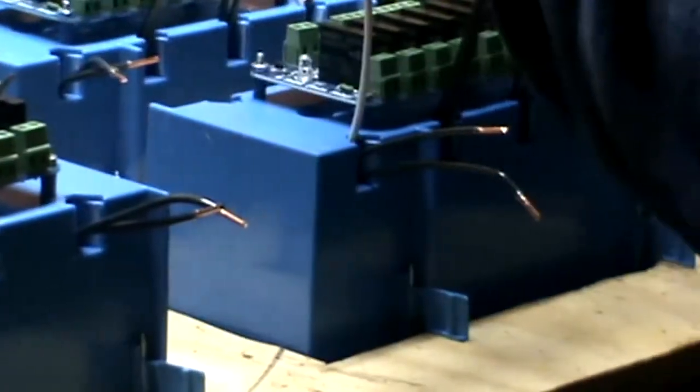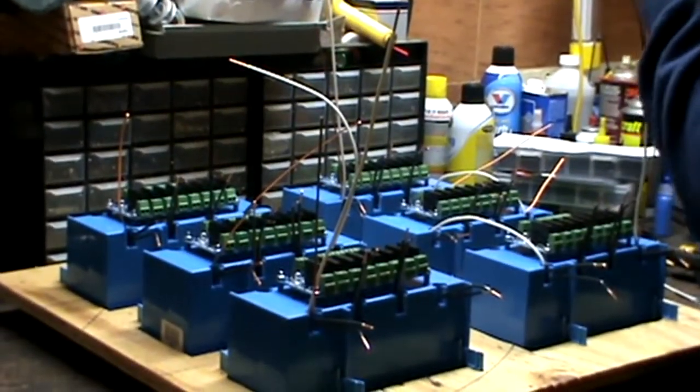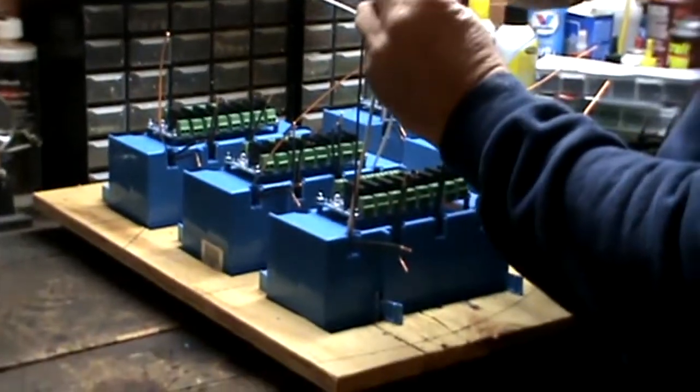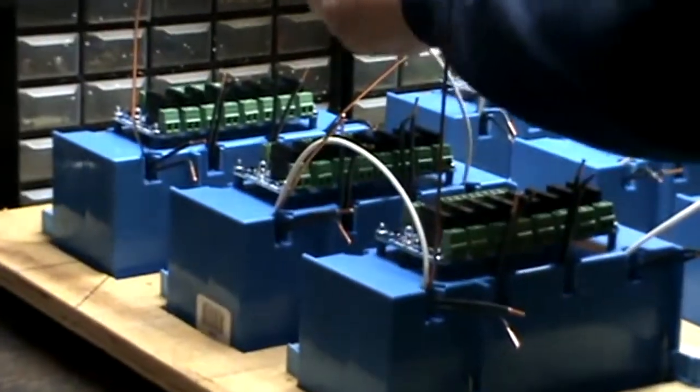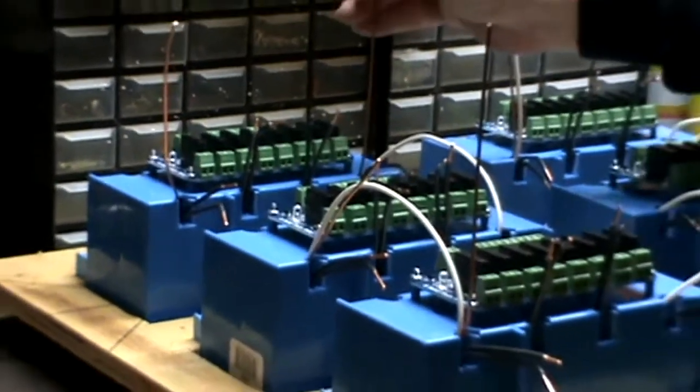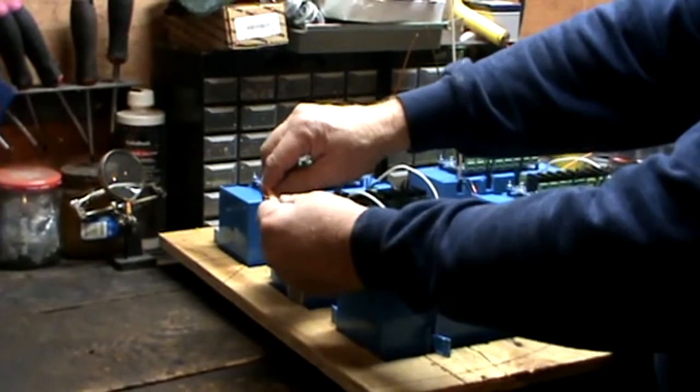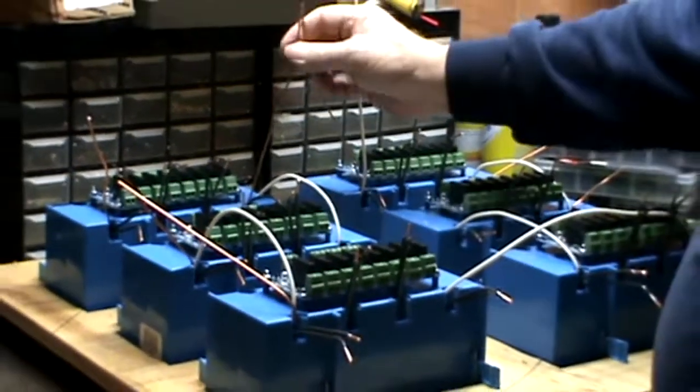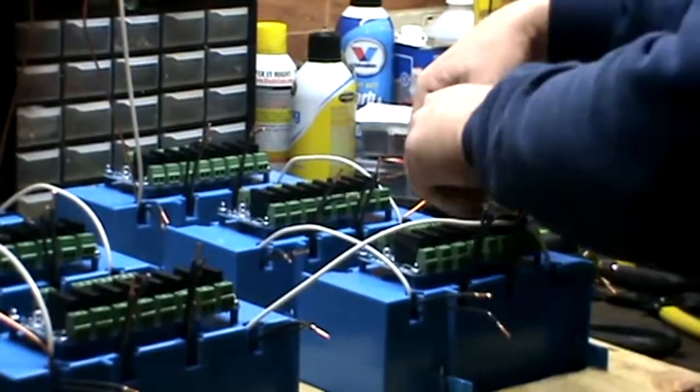Down here, the one on the left, I'm going to slip into the next box. The one on my right, I'm taking it all the way across to the box on the opposite side. Over here, this common simply goes up to the next box, and this one goes to the last box. Now I also have a ground on the opposite side right here. I'm going to connect these two together. Then out here on the side, I'm going to connect the three grounds here. That way, all my grounds will be connected. Both of these are going to be connected together and connected onto the power wire. Over here on the other side, same deal. All three of these will be connected together over here at the side.